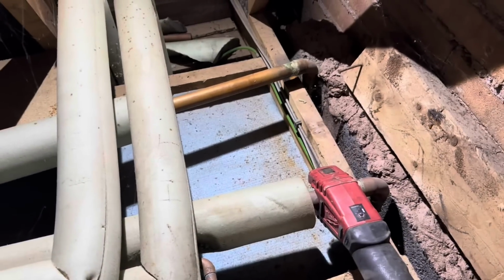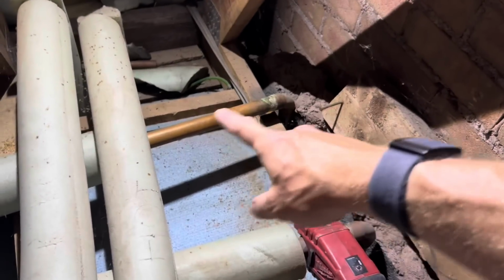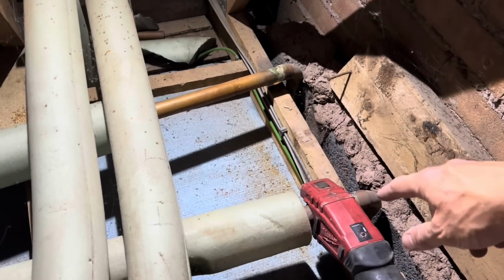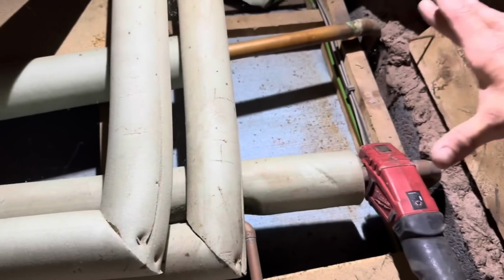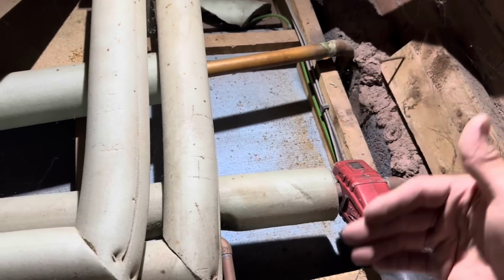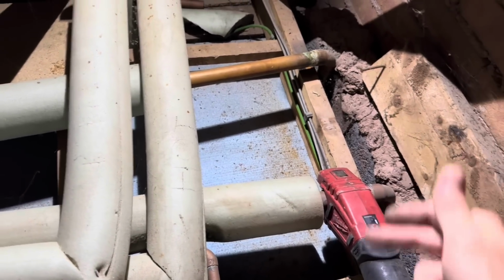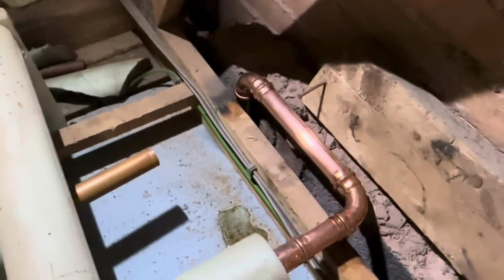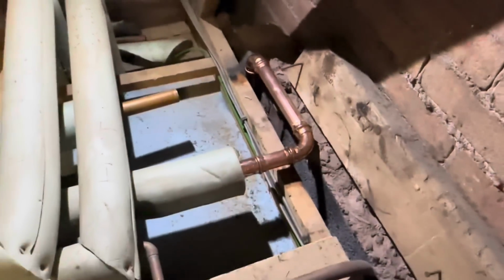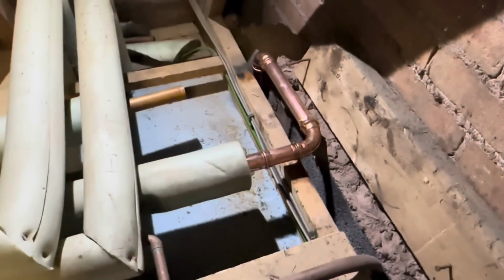So I'm just in the roof space above the boiler, and you can see the 28mm primary flow and return elbowing down. What I'm going to do, because in a minute they just split off like that, is cut them and then try and cross them over, so this one's this side, and then send 2 new pieces down. So literally 2 elbows in a socket. It's going to save a lot of messing around downstairs, and that took, what, 5 minutes?